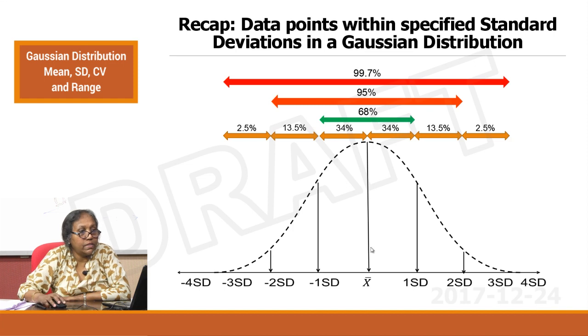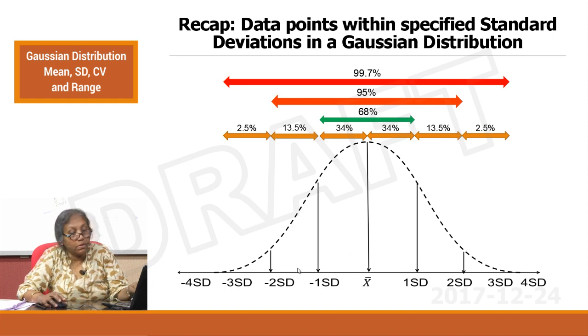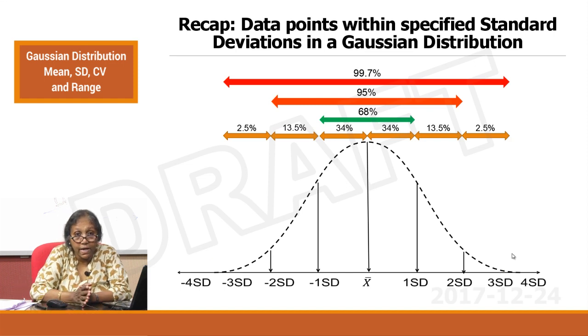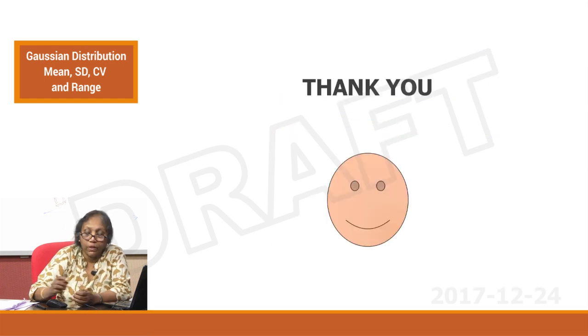To recap: this is the distribution you should see for data points. Anything going outside the 3 SD region is an immediate warning. Any percentage shift — if your 68% is clustering off-center — means the mean has shifted, warning you about systematic errors. If points are spreading to both extremes, that means you are building up random error. All these errors can be detected on the Gaussian curve, and how we use a Gaussian curve in the laboratory we will discuss in later videos. Thank you.